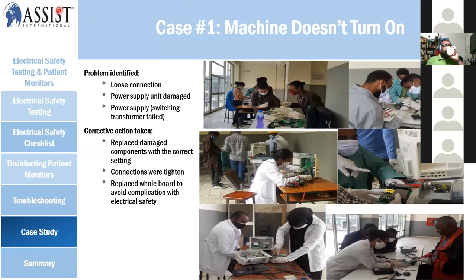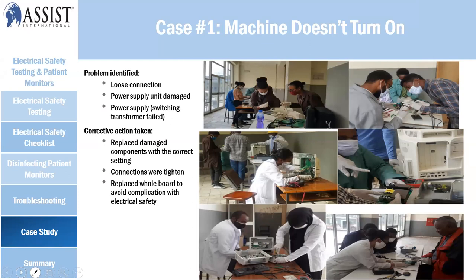The case study covers patient monitoring systems encountered during maintenance work. Case one: machine does not turn on. Identified problems included loose connections, damaged power supply, and a failed switching transformer. Corrective actions taken: damaged components were replaced with the correct settings, loose connections were firmly tightened and fixed, and for the failed switching transformer, the whole board was replaced to avoid complications with electrical safety.